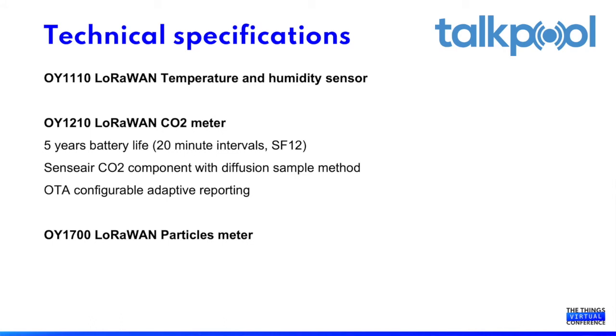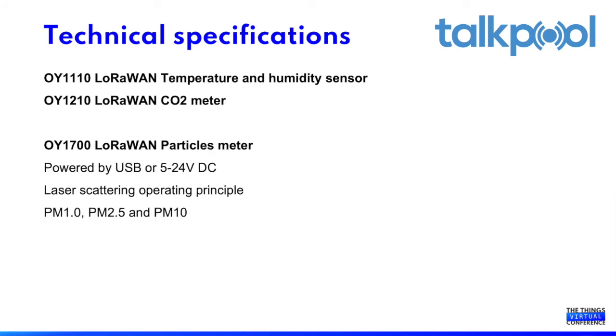And then you have the 1700, the particle sensor. It measures particulate matter PM10, PM2.5 and PM1.0, together with temperature and humidity. It is powered over USB with a USB adapter, but it also supports 24 volt DC, which is quite common in buildings for HVAC applications. It uses laser scattering technology to detect very small particles. Particulate matter is typically the very small smog particles that are very bad for human health, the ones that go far into the lungs.